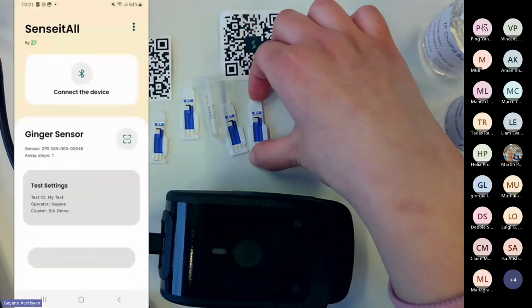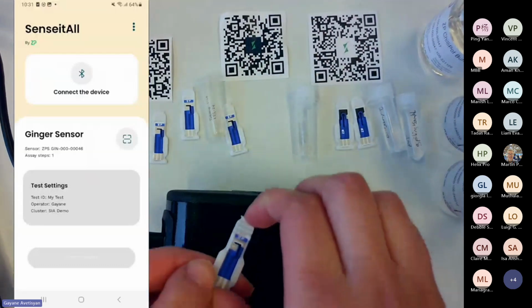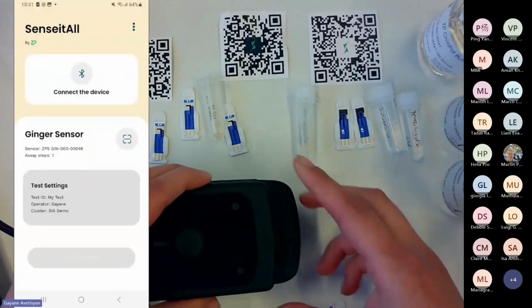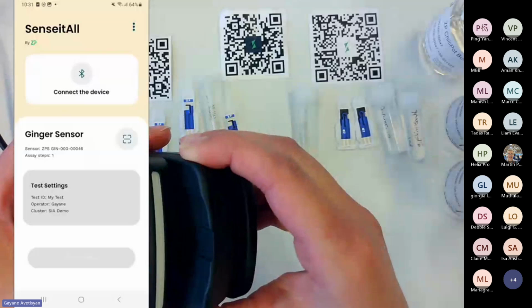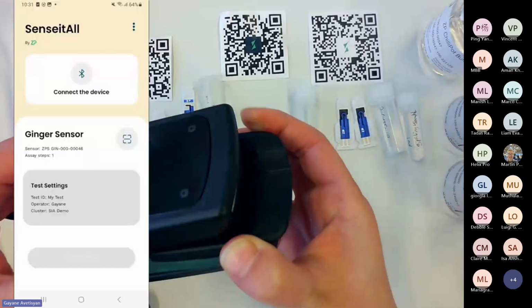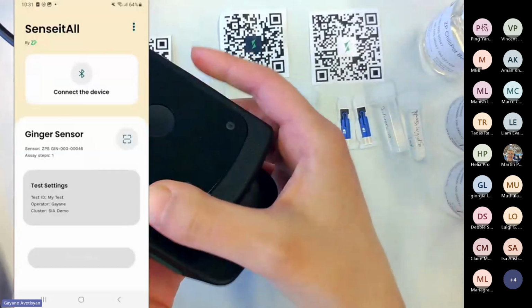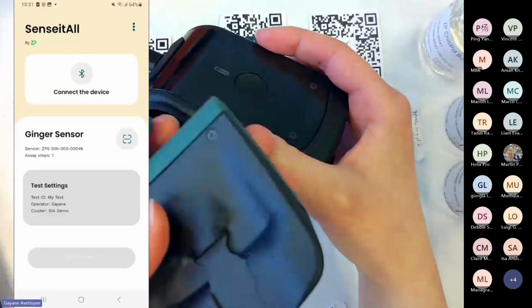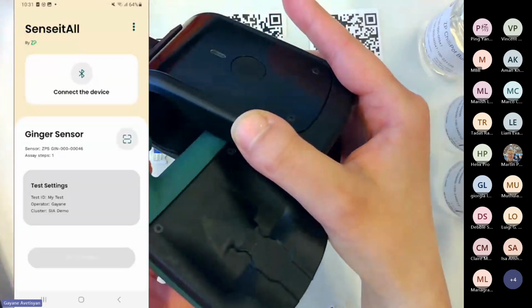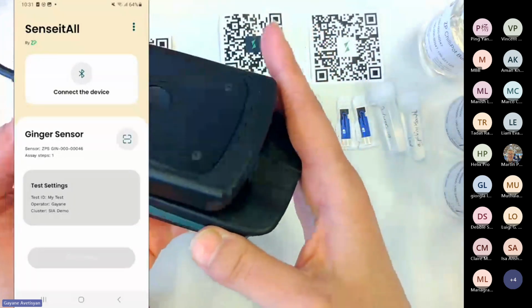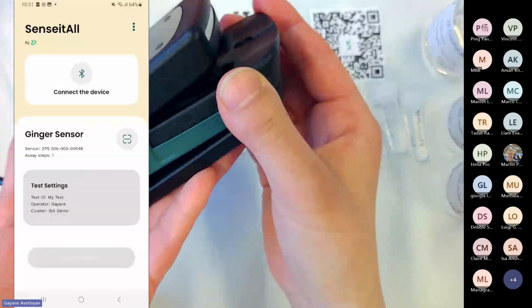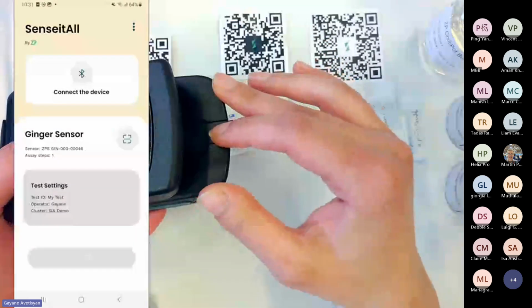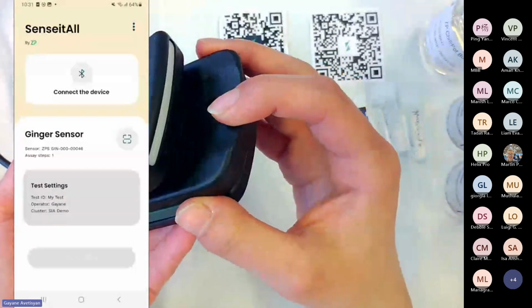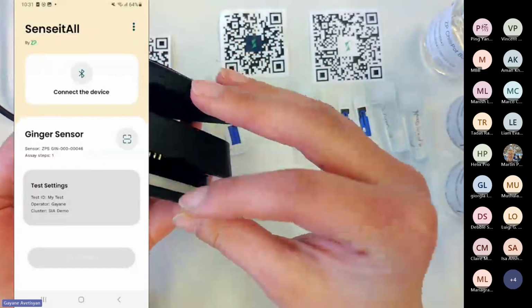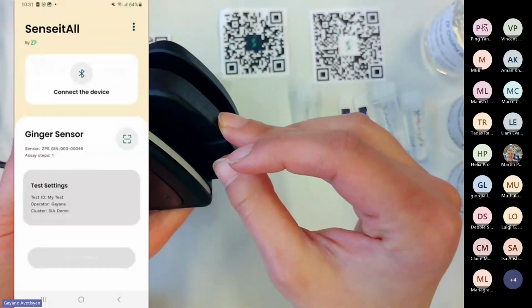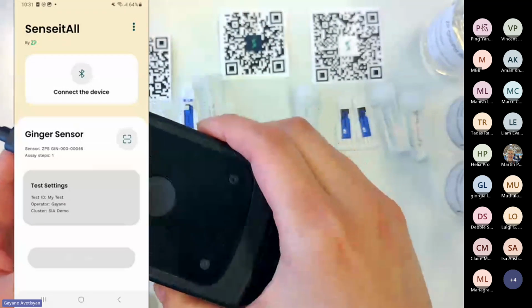So I'll just take the sensor, and I will need to place it inside the device. The device is divided into two parts. This part is the moving one, and this is the main one. They click to each other with magnets, and this moving part goes up and down. So when we are placing the cartridge here and clicking it up, the connectors are joining to the sensor connector, and we will be ready for the measurement.